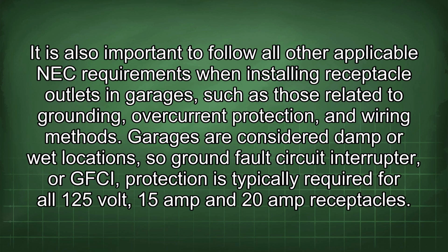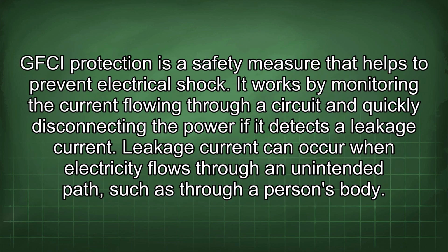It is also important to follow all other applicable NEC requirements when installing receptacle outlets in garages, such as those related to grounding, overcurrent protection, and wiring methods. Garages are considered damp or wet locations, so ground fault circuit interrupter, or GFCI, protection is typically required for all 125 volt, 15 amp and 20 amp receptacles. GFCI protection is a safety measure that helps to prevent electrical shock.